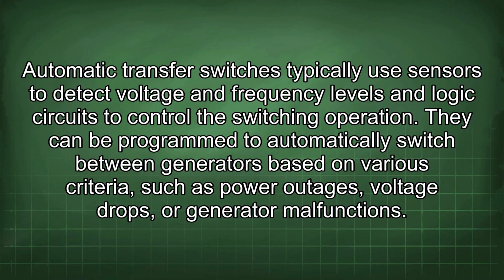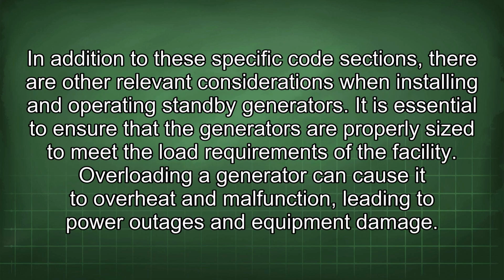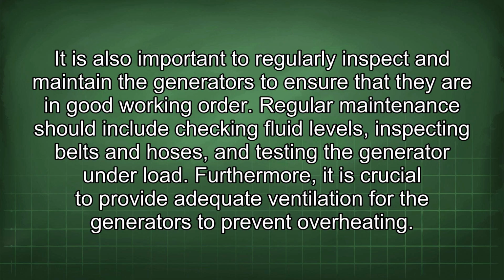They can be programmed to automatically switch between generators based on various criteria, such as power outages, voltage drops, or generator malfunctions. In addition to these specific code sections, there are other relevant considerations when installing and operating standby generators. It is essential to ensure that the generators are properly sized to meet the load requirements of the facility. Overloading a generator can cause it to overheat and malfunction, leading to power outages and equipment damage.